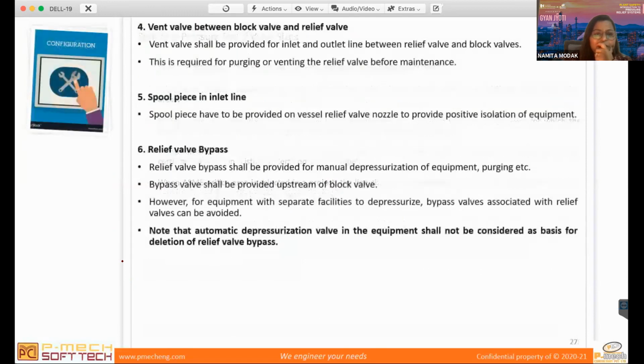Okay, relief valve bypass. It's used when you want to do manual depressurization of your system. Normally BDVs are given for automatic depressurization of the system. So whenever you want to do a manual depressurization, you will give a PSV bypass. It can normally be a globe valve, so you can just throttle it manually and depressurize your system.